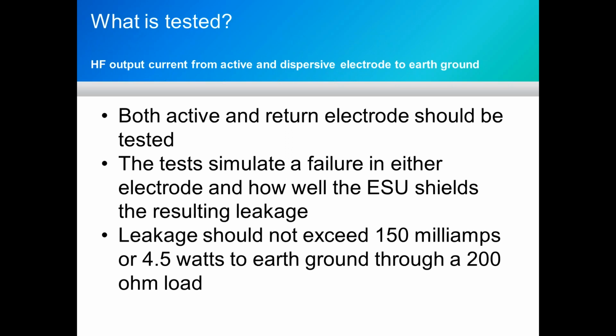A manufacturer can specify something smaller for a particular test, and you'll see folks doing that with bipolar testing or ligature testing, but they can never specify anything higher. The other thing to note when you're doing high frequency leakage testing is we're always setting the generator to maximum power.